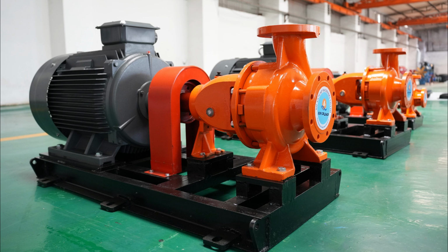Makes sense, pumping water is going to be different from pumping something else. You got it. We got to think about the fluid's viscosity, so how thick or thin it is, temperature, specific gravity, that's like its density compared to water, if it's got solids in it, and, this is important, its chemical makeup. Is it corrosive? All these things affect what pump and what materials are going to work best.